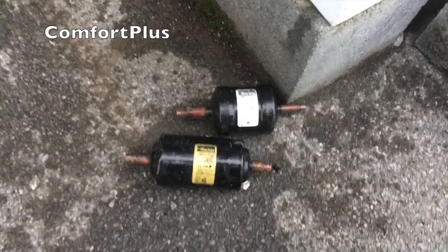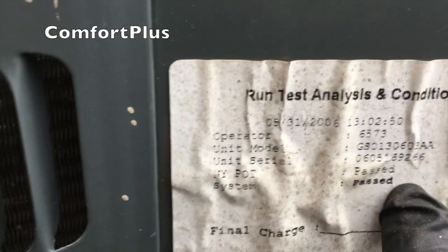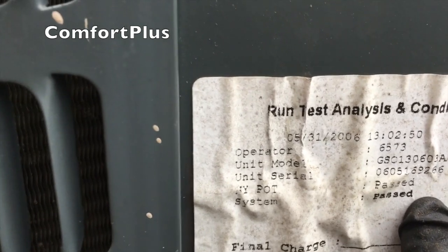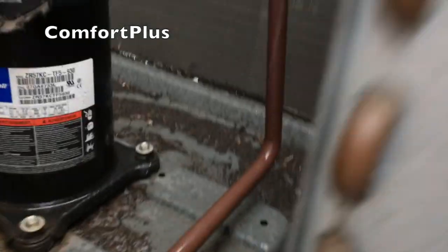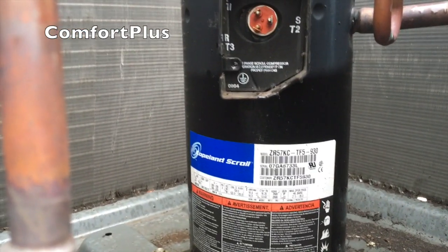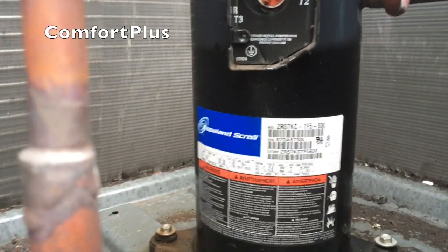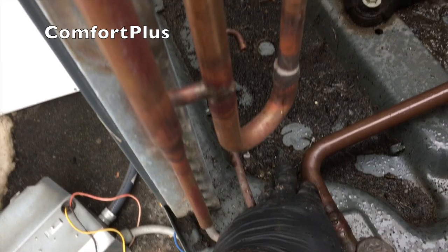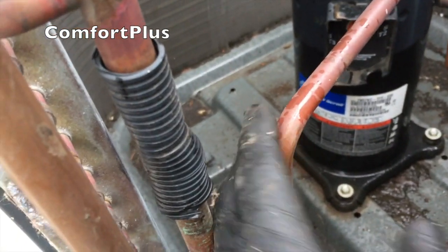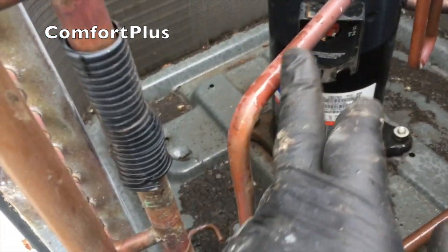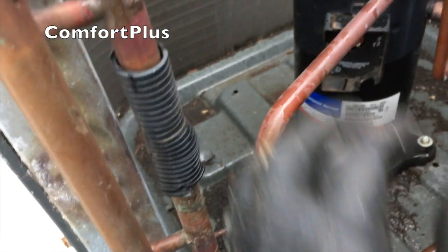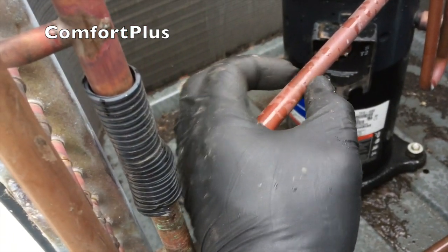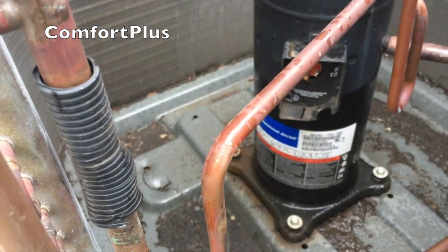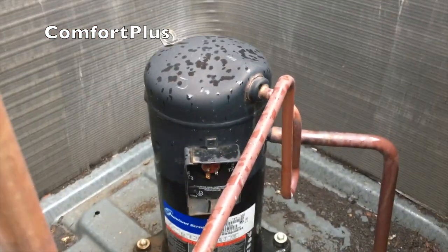Okay, got the old dryers out. Always cut them out. And if you see 2, try to put back only 1. This unit was run tested on May 31st of 2006. The compressor has an 07 serial number, so I guess the first one didn't last long. And since I've cut this dryer out down here, I could take the whole coil off, or probably even easier would be to cut this line here now and set the coil out of my way. I could always swedge it up and put it back together right through this opening. Be a lot easier working conditions. I think I'll do that.